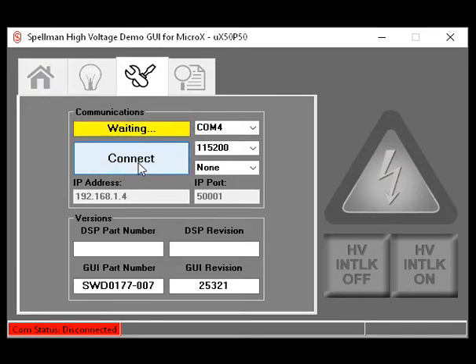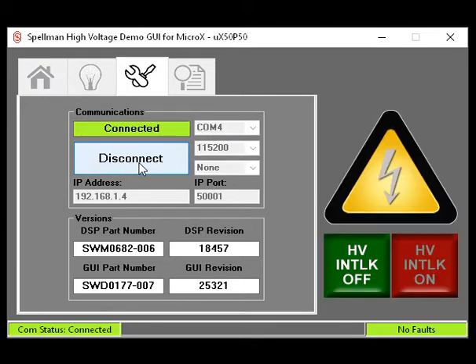Click Connect. The green Connected box appears at the bottom. The COM status is shown as Connected in green and No Faults is displayed in green. The GUI is now connected and controlling the X-ray generator.